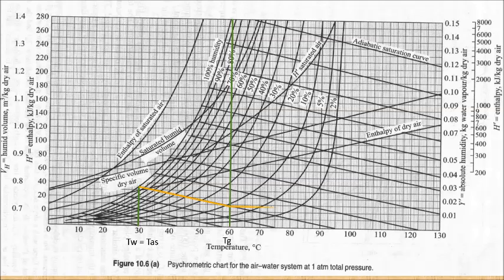From the intersection point, extend the line to the right axis, yielding a value for absolute humidity of 0.014 kg per kg dry air. Then draw a horizontal line from the same point to the left until it reaches the 100% humidity line, and drag the line downwards to obtain the dew point temperature, equal to 21.7 degrees Celsius.